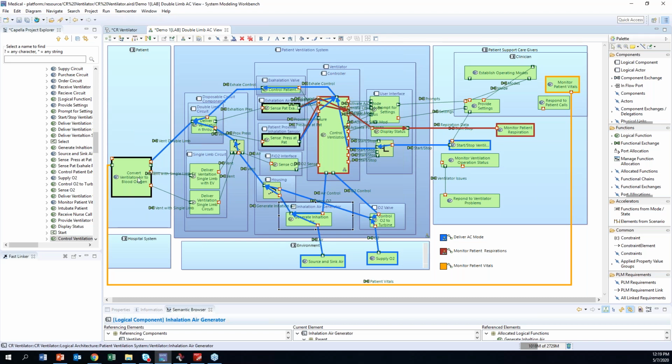There are going to be certain signals that come back from the patient. In this case, they're actually monitoring devices on the hoses of the circuit. That's being fed back, sensing the patient's exhalation right here, and that information then gets shown back on the respirator here.